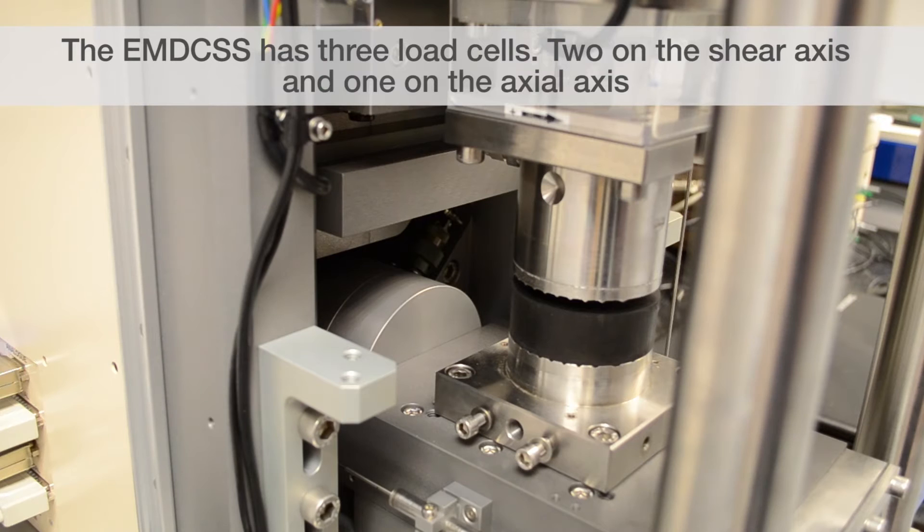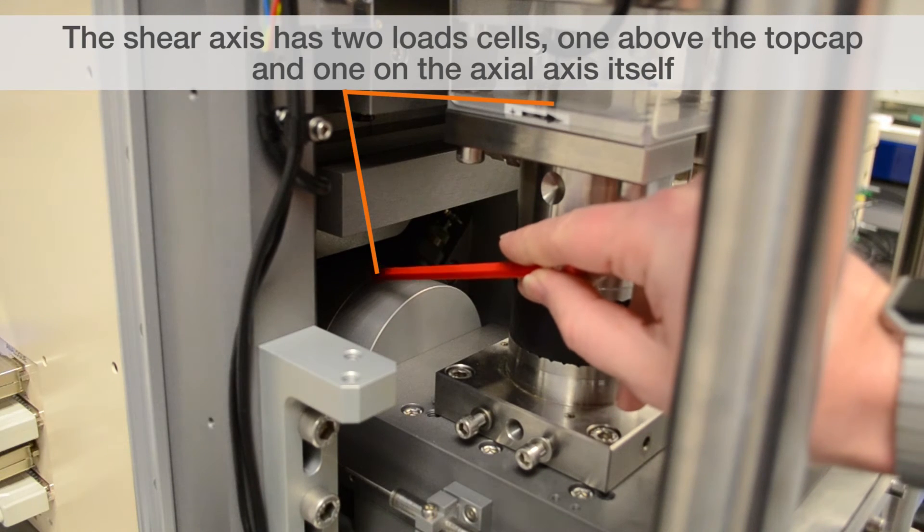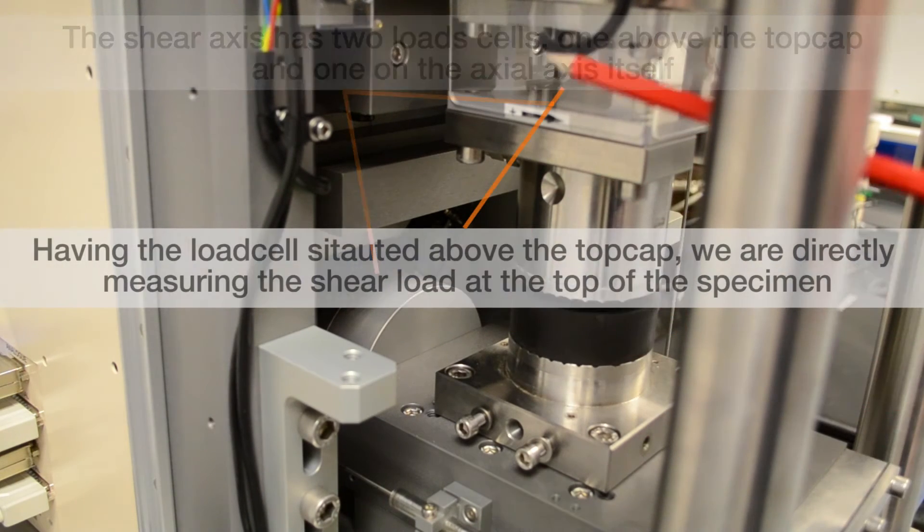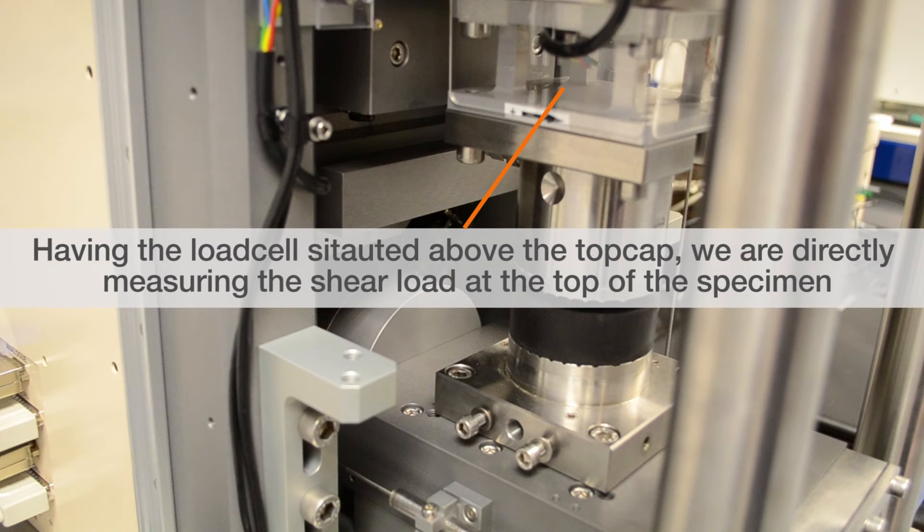The GDS EMDCSS has three load cells that are currently used within the machine. We have two on the shear axis and one on the axial axis. The shear axis has two load cells situated, one here above the top cap and one here on the axial axis itself. Having the load cell situated above the top cap, we are directly measuring the shear load at the top of our specimen.